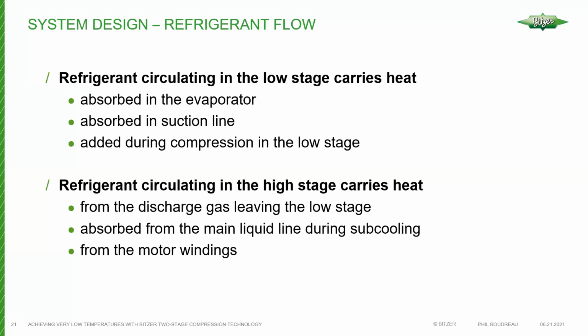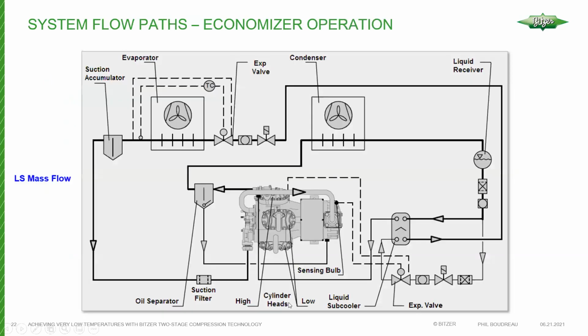Okay, so the high stage has to carry all of the refrigerant that left the low stage, all of the heat that's absorbed from the main liquid line during subcooling, and I'll show you how this works. And also, the interstage is where the motor is located. So the high stage is also going to be carrying that flow. Ultimately, the high stage carries all of the flow. Okay, so what we'll do is we'll follow the flow. We'll follow the refrigerant through a circuit.